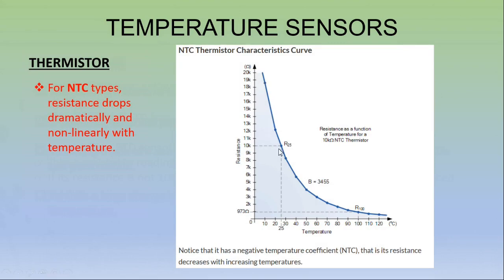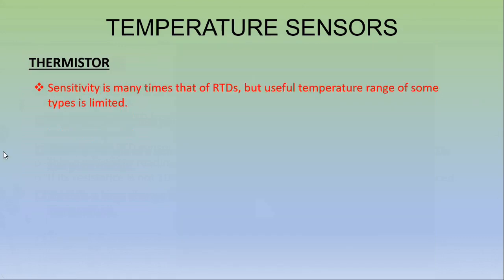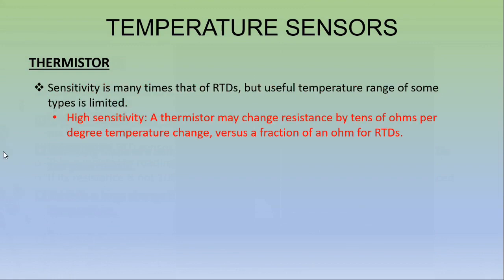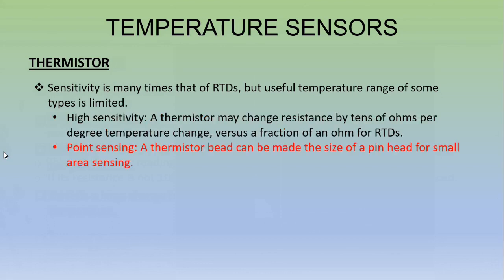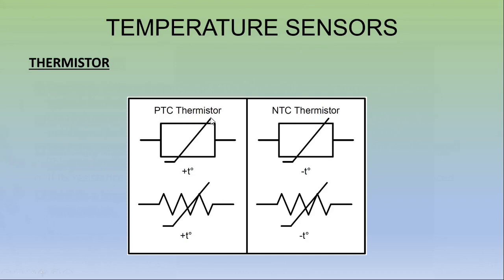Here's a chart showing that. This is a 10 kiloohm NTC thermistor, and you can see how quickly the resistance drops in just a matter of 30 degrees right there. Sensitivity of a thermistor is many times that of an RTD, but useful temperature ranges on some types are limited. With high sensitivity, a thermistor may change resistance by tens of ohms per degree temperature change versus a fraction of an ohm for RTDs. Thermistors can be used for point sensing because the thermistor bead can be made the size of a pin head for small sensing areas. Here are some symbols of them, like a hockey stick.